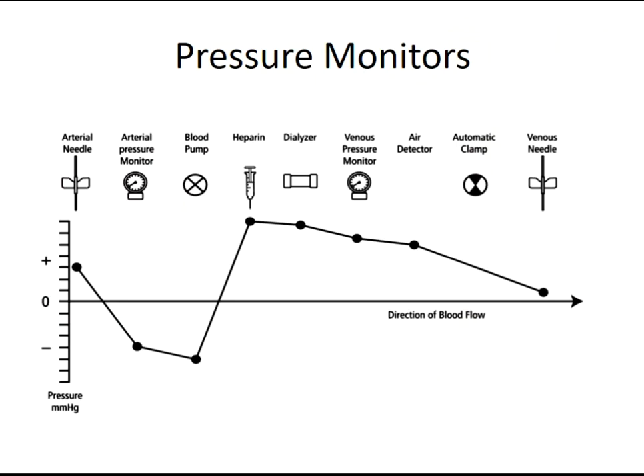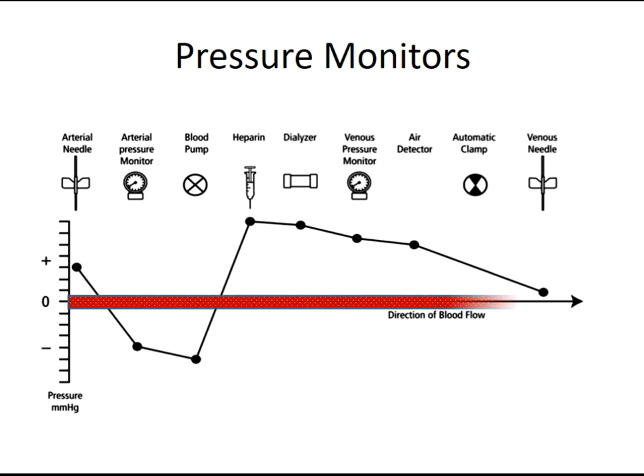The pressure monitors while blood is moving are continuously monitored: the arterial pressure monitor, the transmembrane pressure monitor, and the venous pressure monitor.